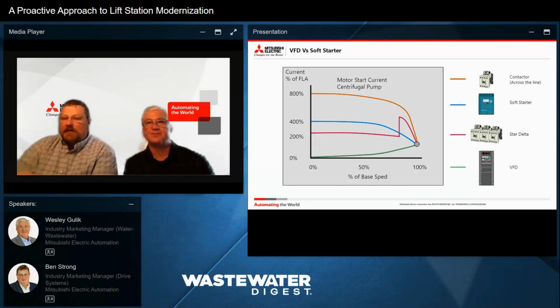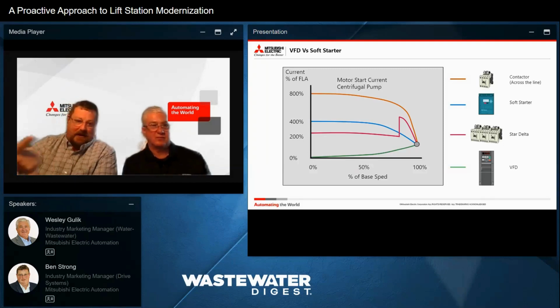So here, talking about the different technologies you need to consider for starting your motors. We've heard arguments from smaller lift station operators, smaller municipalities, maybe it's more rural, maybe it's older, that, I really like a contactor to operate. Just my pump only turns on, it only turns off. A contactor is binary, it's very easy. But there's some drawbacks to just operating on a contactor. All the information you'll ever get back out of a contactor is it's on or it's off, unless you add current transformers.